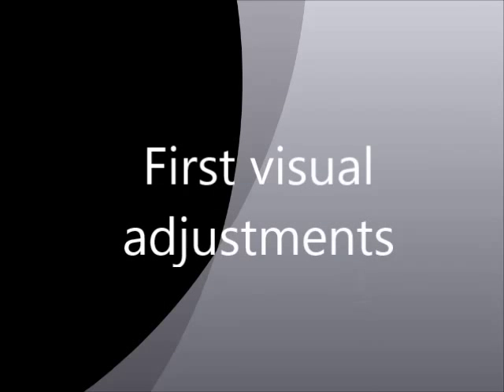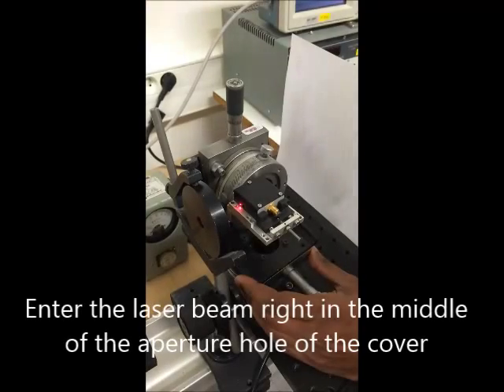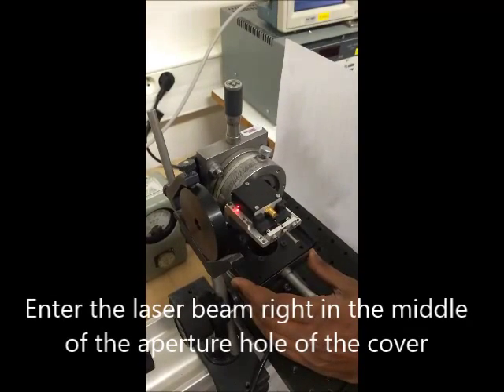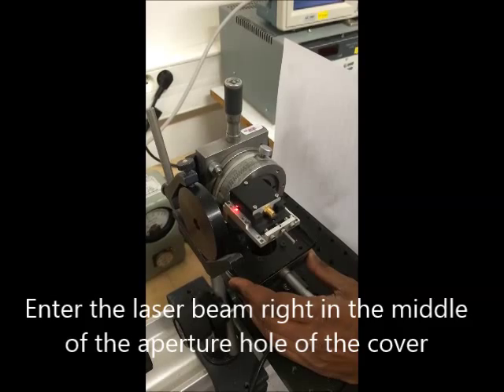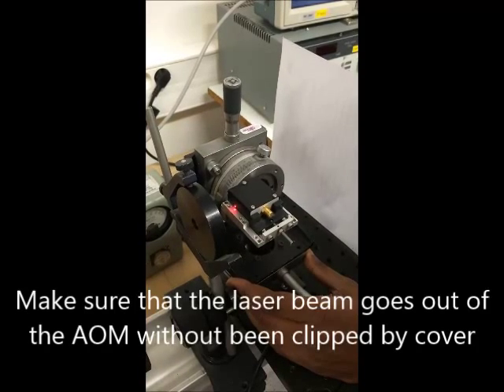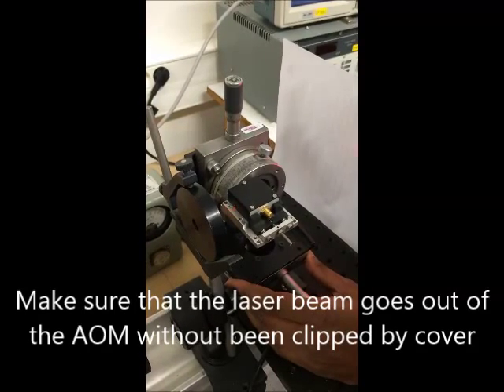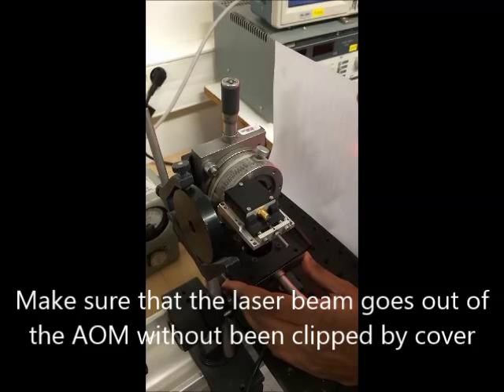First visual adjustments. First of all, enter the laser beam right in the middle of the aperture hole of the cover. Make sure that the laser beam passes through the modulator without being clipped by the cover.